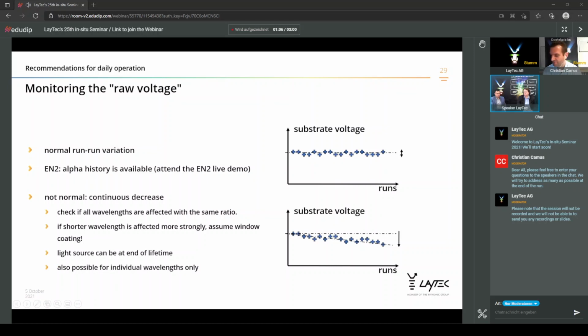Regarding the end of lifetime, you receive together with the LayTec system a calibration protocol. This is maybe very important to mention, as not everyone is aware of that. It clearly states what voltage we measured with the same optical path on the silicon wafer, and you can compare it to your current value. The decrease is possible for individual wavelengths as well.